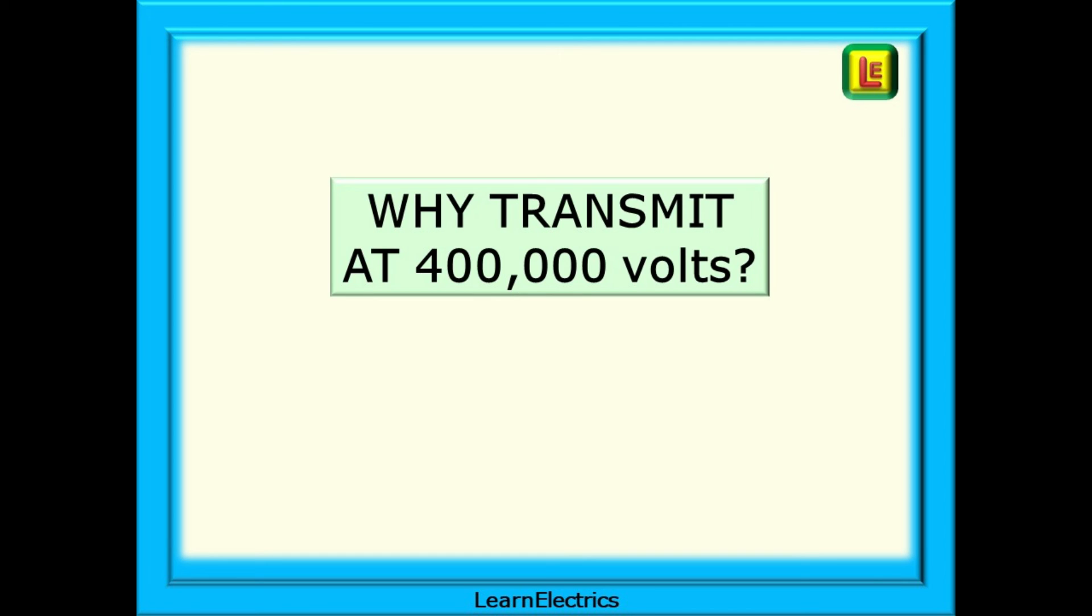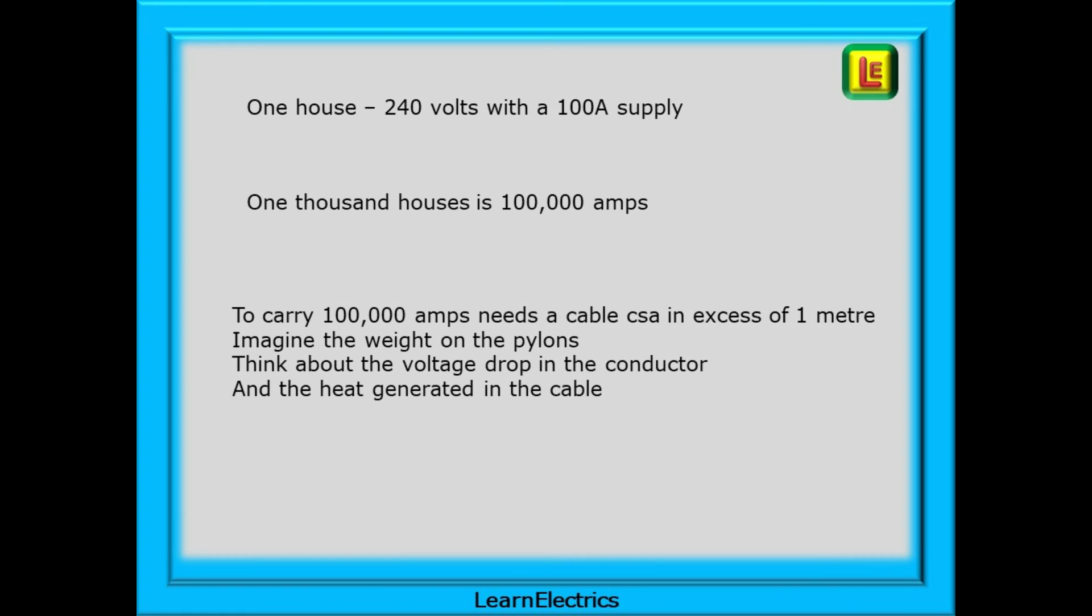The final question for this video is why do we transmit at 400,000 volts and go through all this palaver of step-up and step-down transformers? And isn't 400,000 volts a lot more dangerous than 230 volts? Well, let's look. Keeping the maths very simple, if we have one house with a 240 volt supply and a maximum demand of 100 amps, then 1,000 houses will require 100,000 amps. To carry 100,000 amps with a 240 volt supply, we will need a cable with a cross-sectional area in excess of one meter. Imagine the weight on the pylons for mile after mile across the landscape, and think about the voltage drop in the conductors. It's going to be massive, not to mention the heat generated in the cable as well. And that is just for a thousand homes. In reality, this could be many thousands of properties with many thousands of amps required.